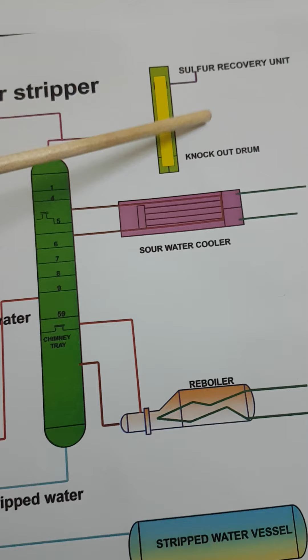And as per the industrial norm, atmospheric condition, and environmental regulation, we can send only 10 ppm to the flare, and the remaining we cannot send, as it is harmful to the environment. So that is why we don't send this hydrogen sulfide gas to the flare. We send it to the sulfur recovery unit. In case there is a problem in the sulfur recovery unit, if high pressure builds up, at that time we send this gas to the flare to remove the pressure in the column. We have this option, but it is a temporary solution, not permanent.